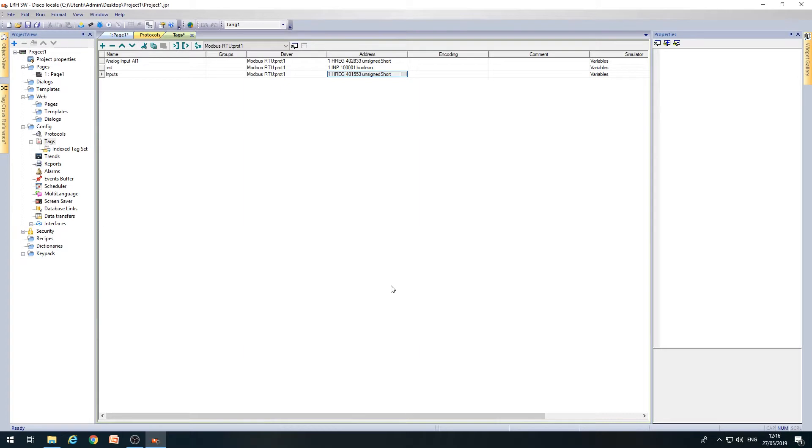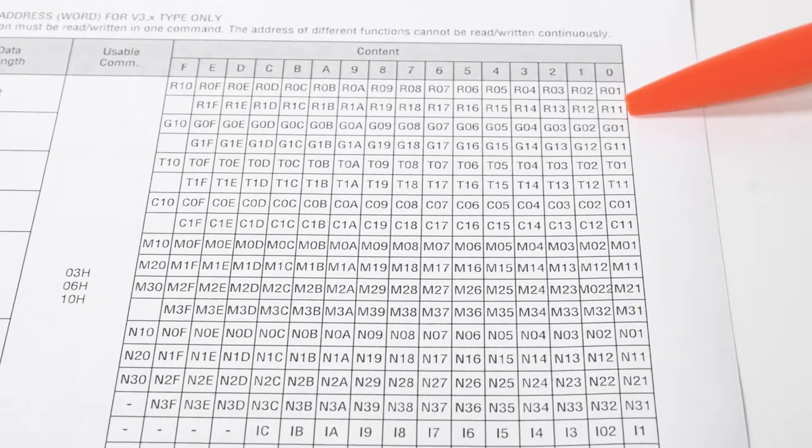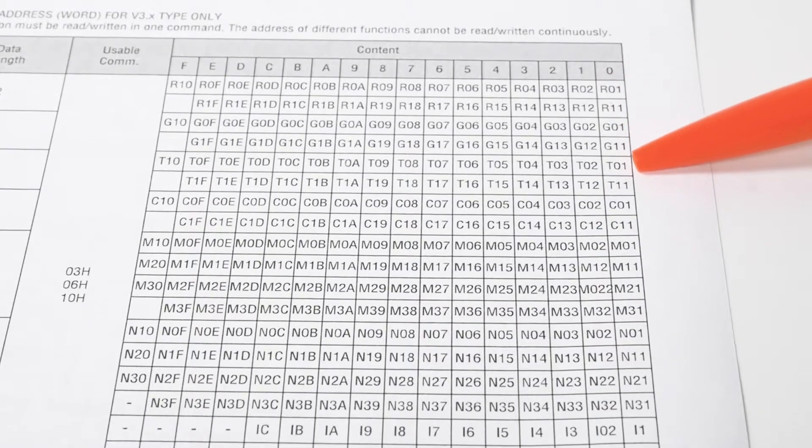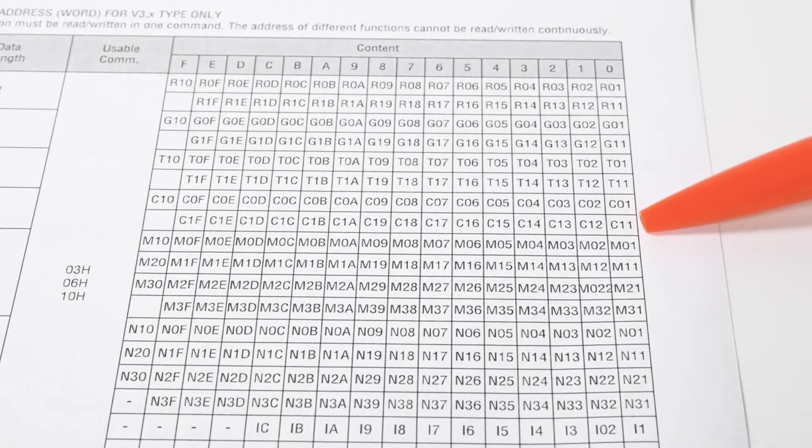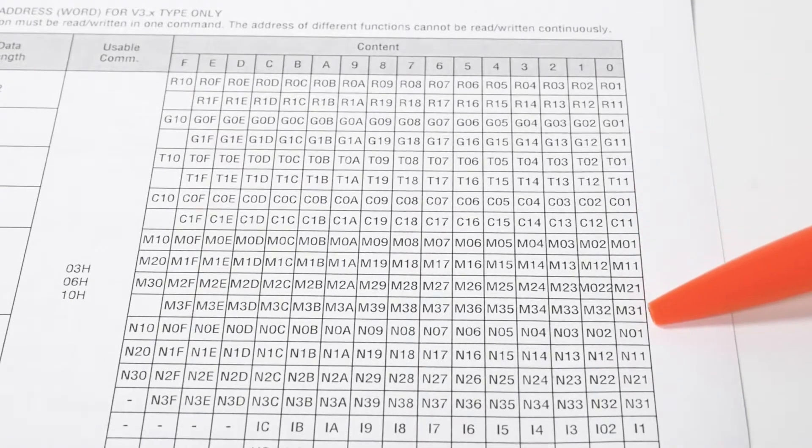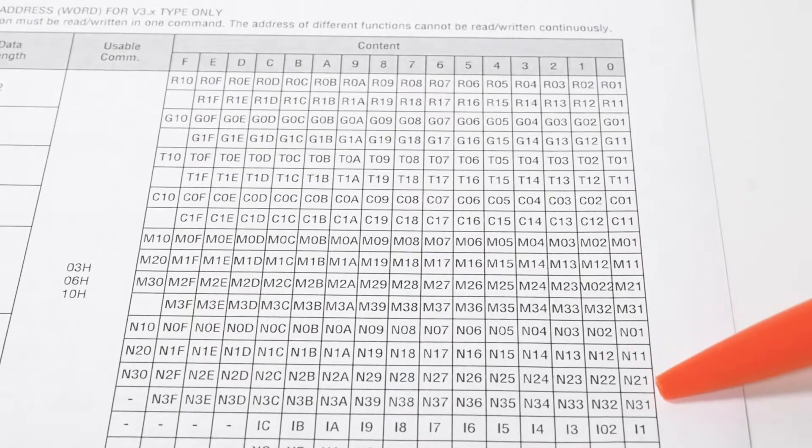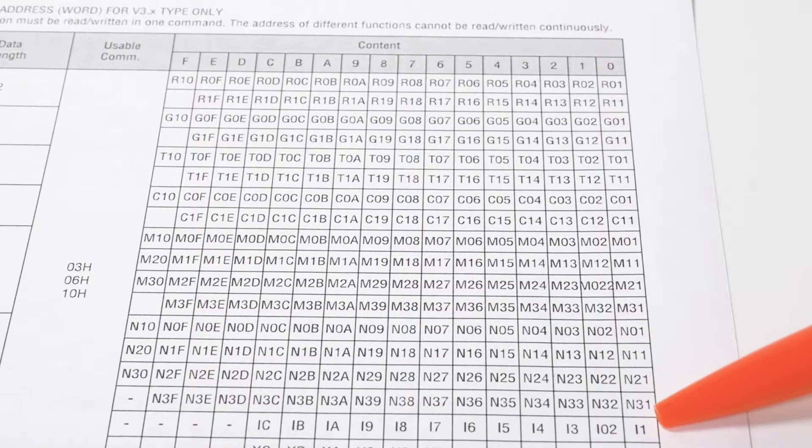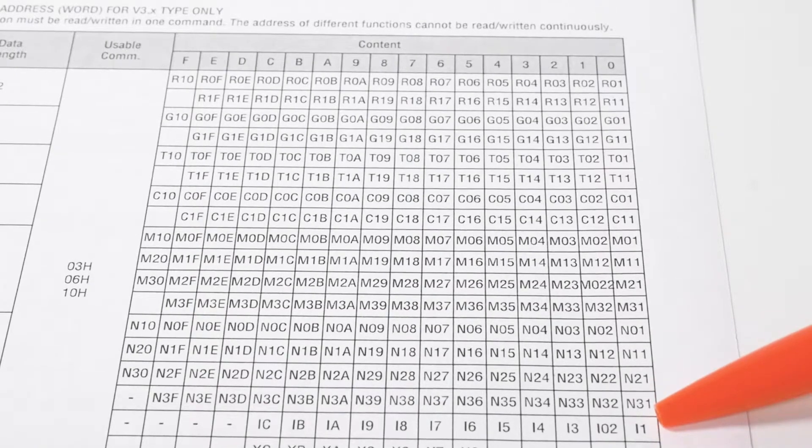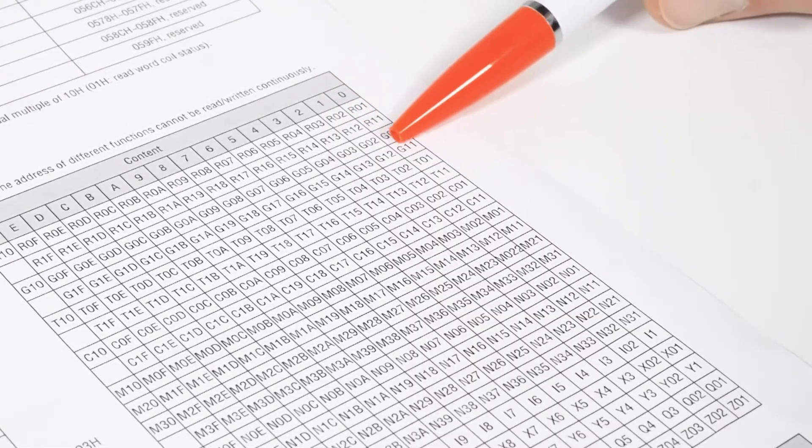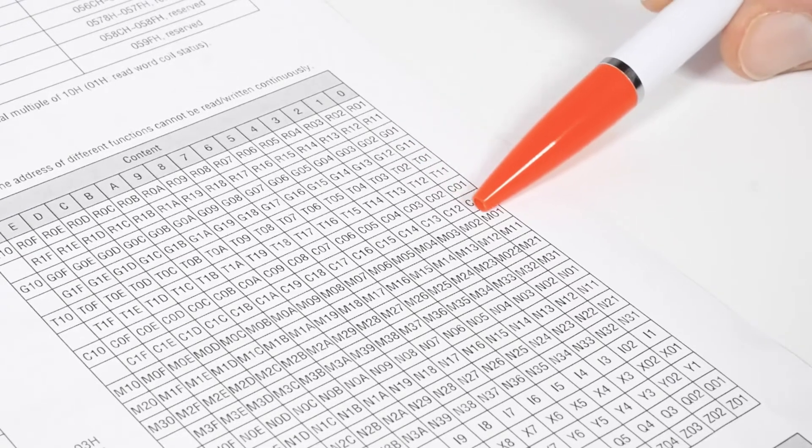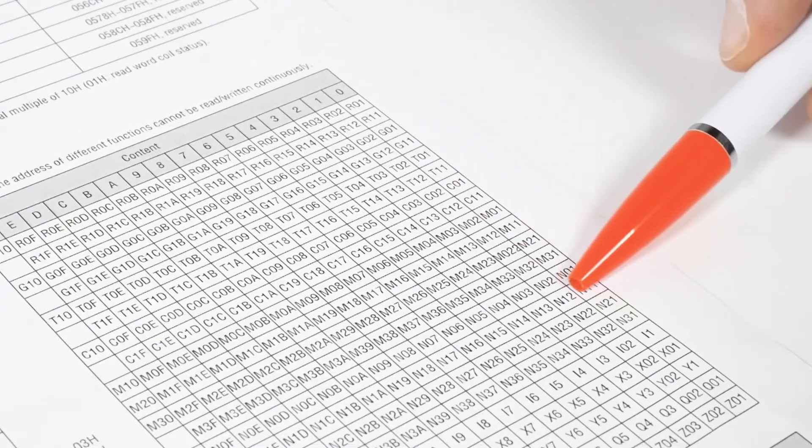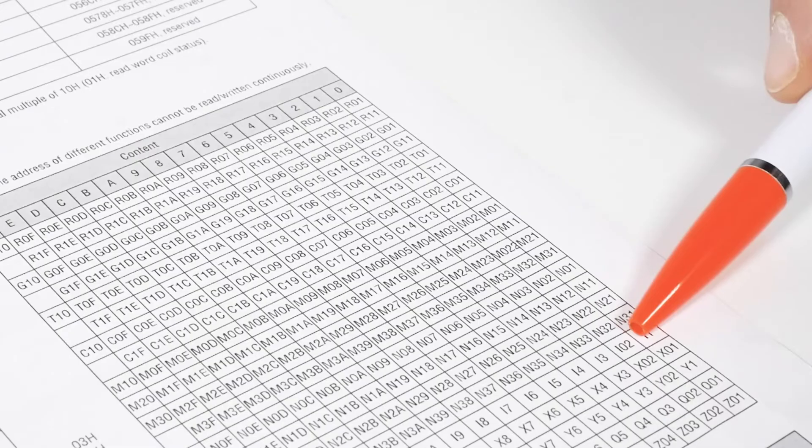Now the tag has been created and can be used within the project. Reading this tag, the micro PLC will respond with a value that, interpreted in binary, will contain the status of all the digital inputs of the micro PLC. As you can see from the Modbus table, bit 0 will be the status of input I1, bit 1 will be the status of input I2, and so on.